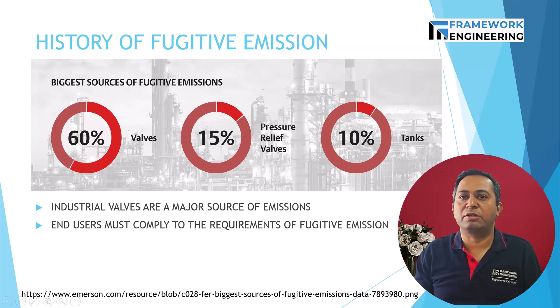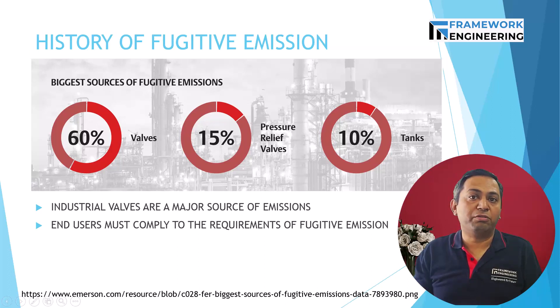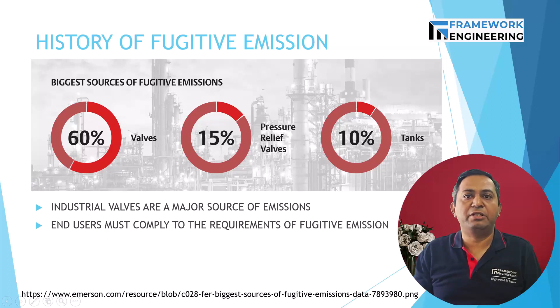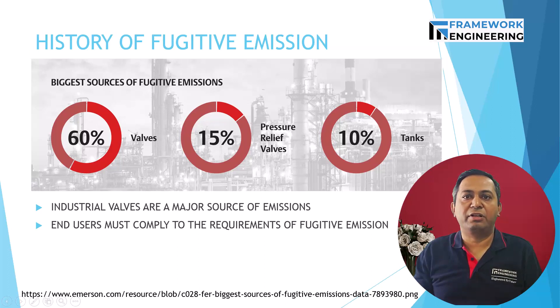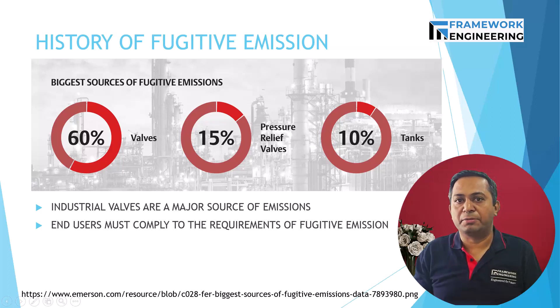But the amount of emission that comes from that small percentage of valves can range from a few pounds up to a ton of emissions. The major causes of valve leakages are aging, damage, and improper installation or maintenance. Seal or gasket failures due to normal wear or improper maintenance are a major cause of these valve emissions.